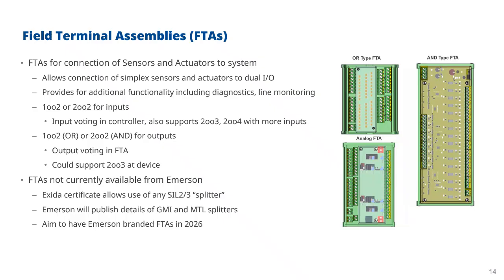So again, we have this option of voting, 1 out of 2 or 2 out of 2 for the inputs. We do support input voting in the controller, and by using more inputs beyond the standard dual input arrangement, you could support 2 out of 3 or 2 out of 4 by using additional inputs. I don't see much demand for that, but 1 out of 2 or 2 out of 2 would be common. On the output side, you can do 1 out of 2, which would be like an OR arrangement, or 2 out of 2, which is an AND arrangement.